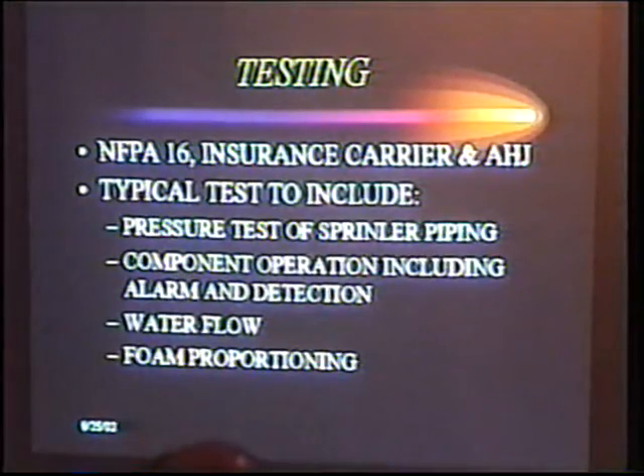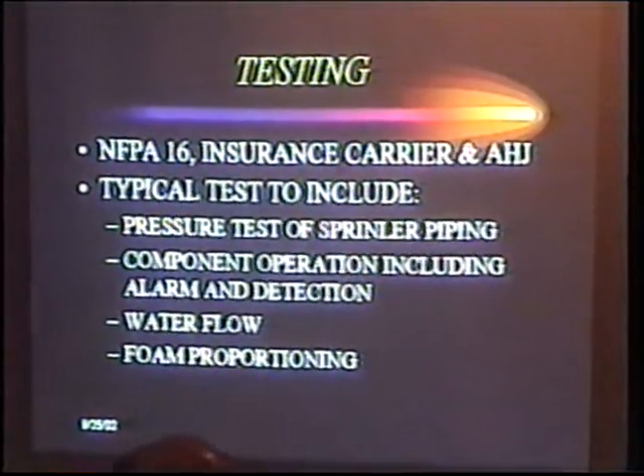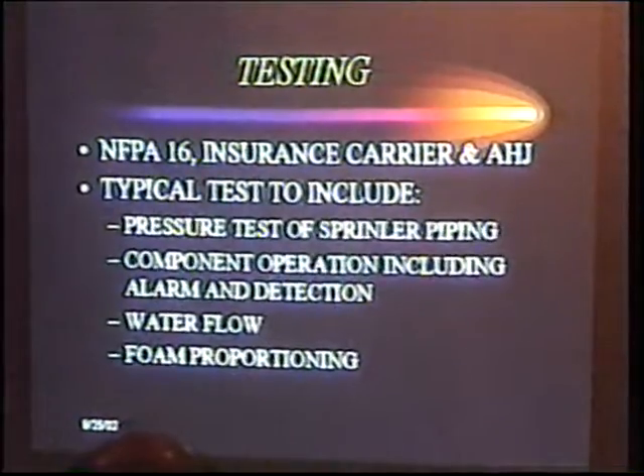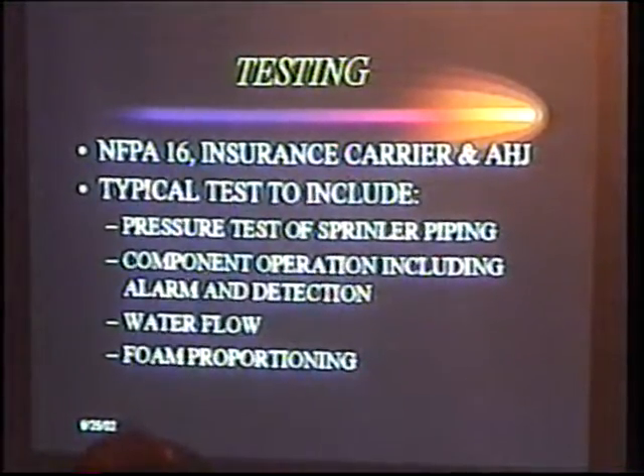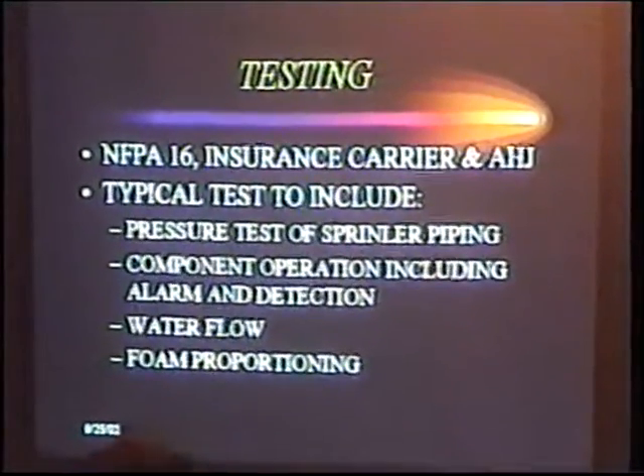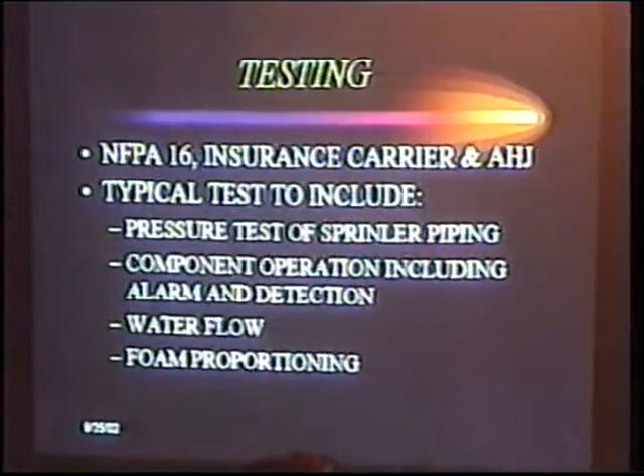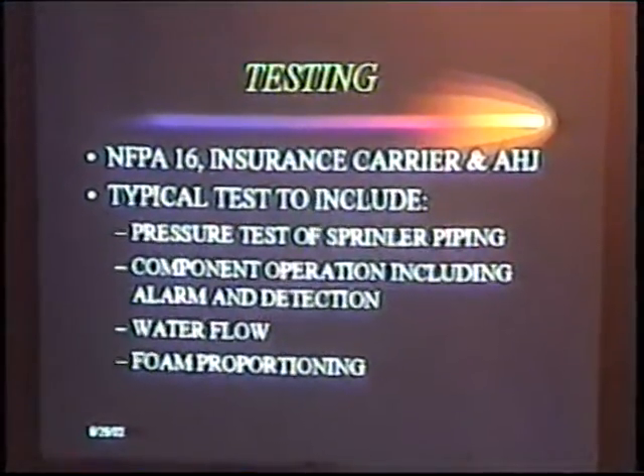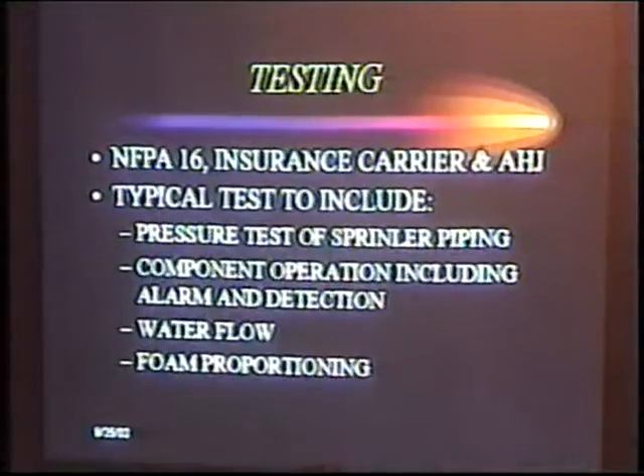This doesn't include everything, obviously. You're going to test your sprinkler piping, hydro test. They don't include the bladder tank. Bladder tank's already been hydro tested. You want to keep that isolated. If you run water into that bladder tank and squeeze that bladder down around the internal tubing, you're going to end up damaging something.